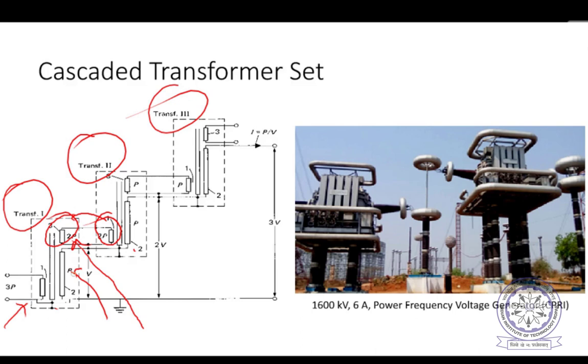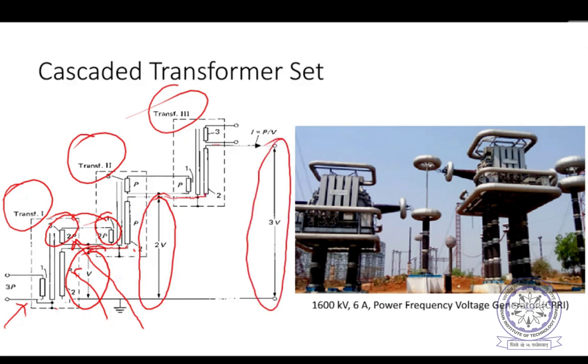The secondary voltage of the first transformer is V, and the second transformer's secondary is connected to the top end of the first transformer's secondary. That's how the voltage gets multiplied, 2 times, 2V. If you use another transformer like this, it becomes 3V. So if you have N transformers connected in series, you can generate NV at the output. But this has certain disadvantages, of course. For other power equipment other than cables it can be used, but for testing cables it creates some problems.